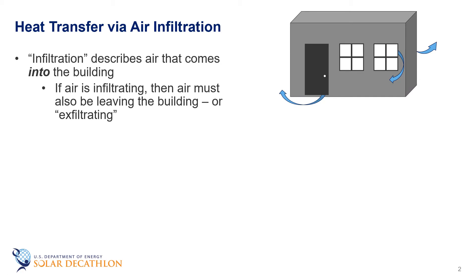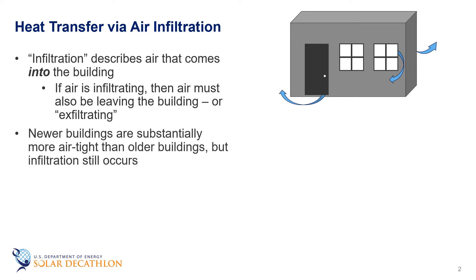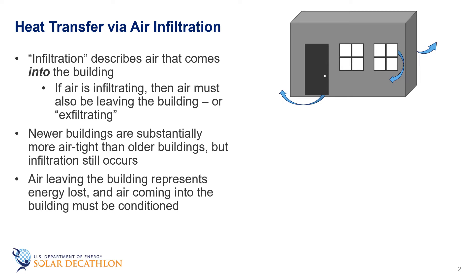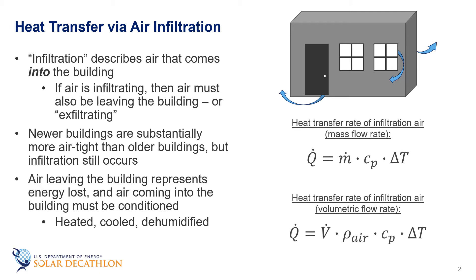In a previous episode we discussed the impacts of infiltration and exfiltration. We said that building envelopes are filled with cracks and have materials that are permeable to air. In older buildings these show up as cold drafts in the wintertime and can also cause comfort issues. Most new buildings have substantially reduced these leaks, but they are still there. Air leaving buildings is energy lost and the air that comes in must be conditioned — either heated in the heating season or cooled and dehumidified in the summertime. We discussed the equations to calculate this heat loss or gain in a previous episode and realized that it can be a significant portion of the total heating and cooling needs of a building.